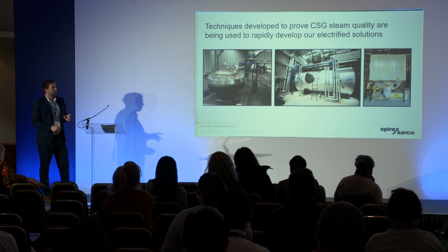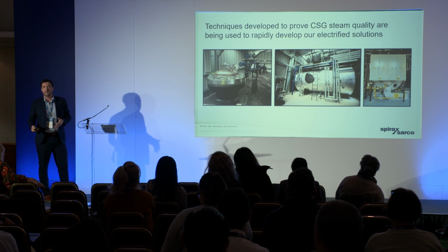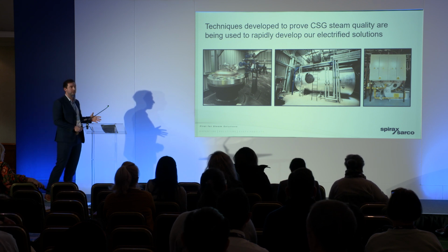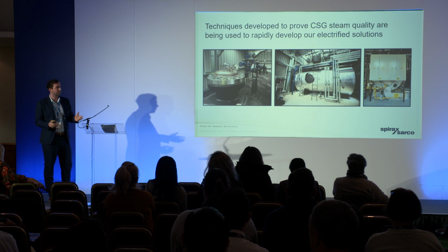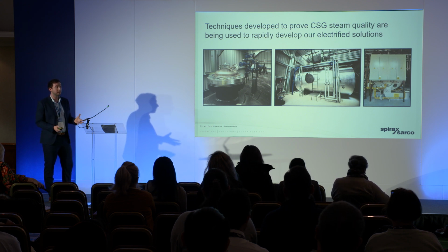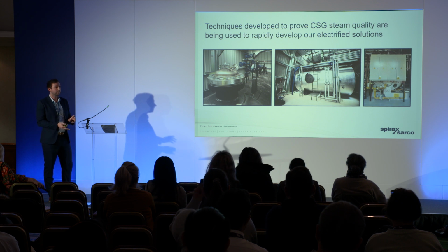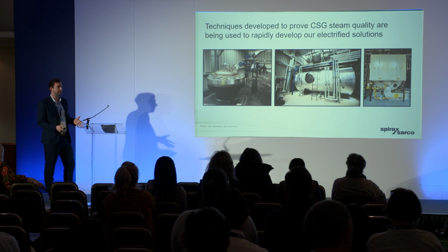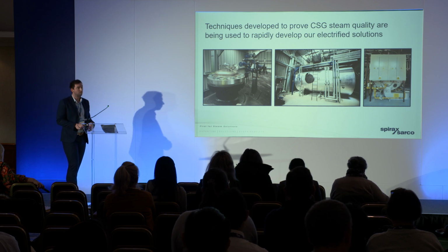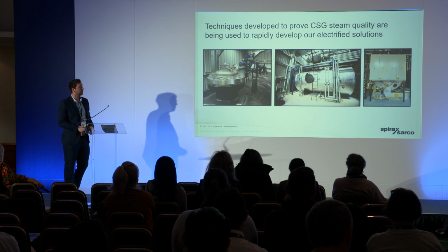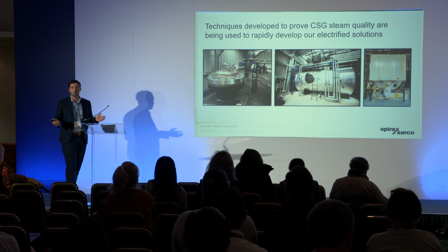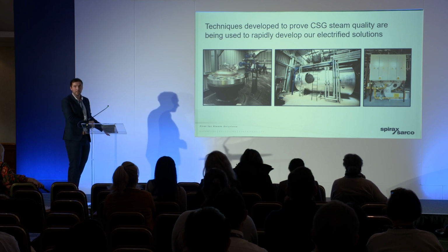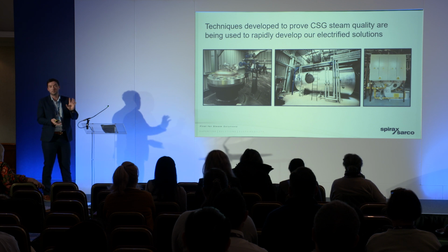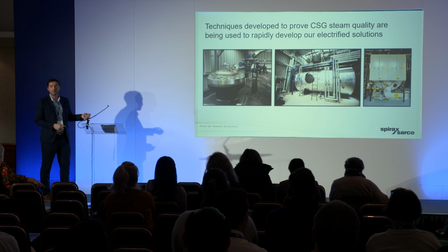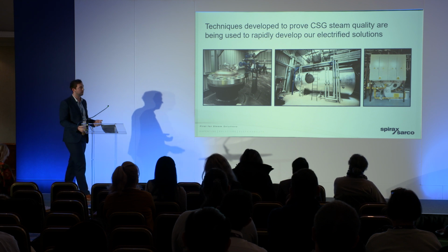We've also got what we've called an electrofit. This is an electrical retrofit of existing gas boilers. I imagine the majority of the steam on the sites you guys are from is generated using natural gas, especially in the UK. So big assets, well maintained, big capital bits of kit, and all of the valve gear and pipework associated with that is already in situ. It's already been invested in. So this solution that we've developed to take to market is basically a way of opening the doors, taking the gas burner out, throwing that away, putting electricity into the boiler with some elements, closing the doors again, and firing it up as an electric boiler. So everything else remains the same.